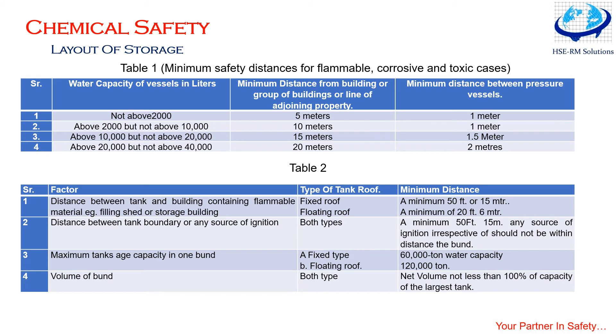As a quick example from the tables: if the water capacity of a vessel is not above 2,000 liters, the minimum distance from a building or group of buildings or adjoining property boundary is 5 meters, and the minimum distance between pressure vessels is 1 meter. For tanks and buildings containing flammable material or filling sheds, whether fixed or floating roof type, the minimum distance is 50 feet or 15 meters, with a minimum of 20 feet or 6 meters in some cases. The distance from the tank boundary to any source of ignition should be a minimum of 50 feet or 15 meters, irrespective of the tank type.